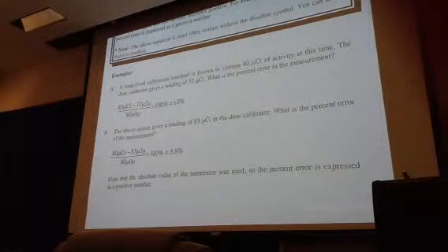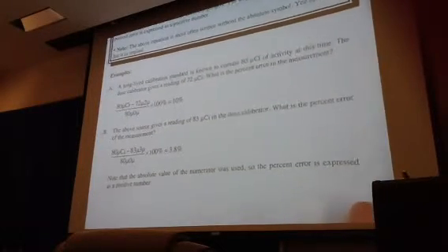Now, there is a third source that we use if you routinely use iodine. Which one is that? 125? Iodine-125? No. Remember, what's the energy of I-125? It's about 35 and 27, isn't it? Which is way far away from that. Barium 133 is the one that we use, because it has an energy that's close to 365 or 364 keV. So you try to select radionuclides that are within the energy range of what you use. This is one of the quality control tests that we use.